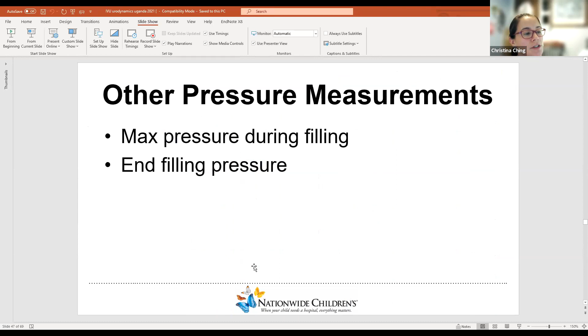Some other pressure measurements would be documenting the maximum pressure during filling and then the end filling pressure. Those measurements are just for understanding what they are, demonstrated here. I don't know how important those are, to be honest, in my clinical decision-making for a patient, but they are some of the endpoints that can be recorded in urodynamics. This is the maximum pressure during the study, and I'm not measuring during a contraction or overactivity, I'm looking at the baseline where it returns to. The maximum pressure here is about 21, just eyeballing it, or you could maybe even do 22, although is that a little bit of overactivity there? And then the end filling pressure is the filling pressure at the end of the study.